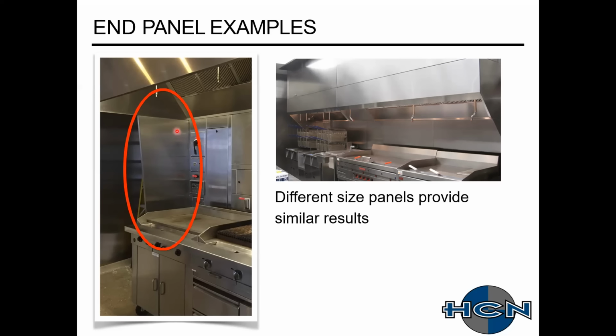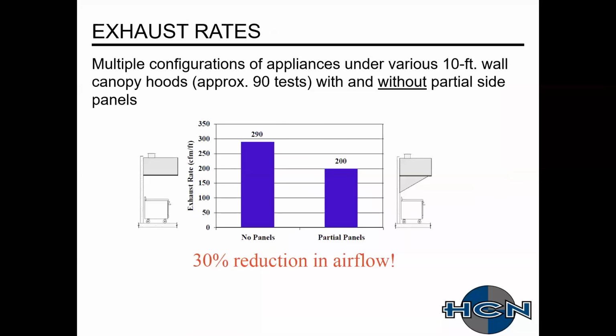The main concept here is by adding those panels, we're reducing the exhaust rate needed and lowering that energy cost, making that ductwork smaller, making that makeup air requirement less as well. So you're improving the overall design by using less. As this was done at the Food Service Technology Lab, they tested, I think, over 8 or 9 different manufacturers with and without end panels. They used partial panels, full panels through the testing, but basically what they found was with panels, you were reducing your exhaust load by 30% typically.